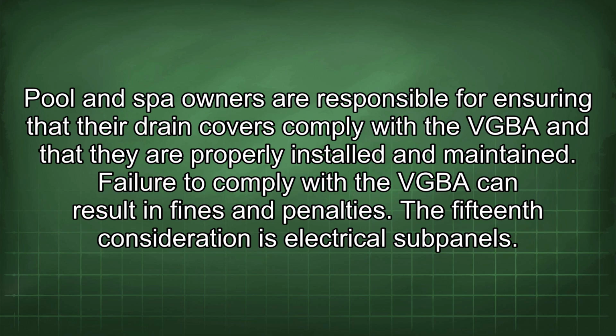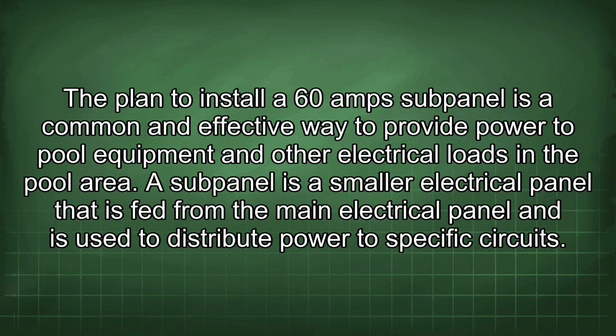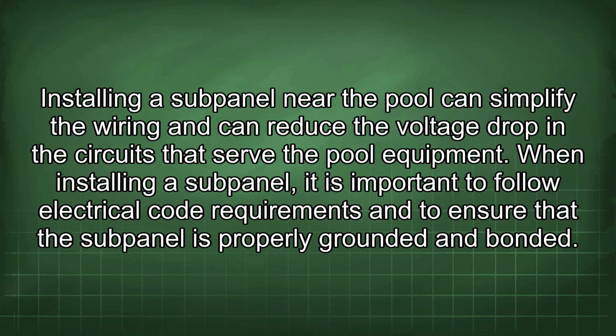The 15th consideration is electrical subpanels. The plan to install a 60 amp subpanel is a common and effective way to provide power to pool equipment and other electrical loads in the pool area. A subpanel is a smaller electrical panel that is fed from the main electrical panel and is used to distribute power to specific circuits. Installing a subpanel near the pool can simplify the wiring and can reduce the voltage drop in the circuits that serve the pool equipment.